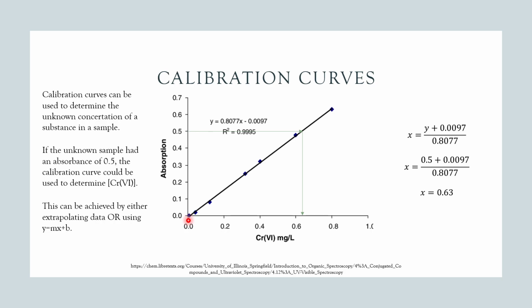So again, you would make up your chromium standards of set concentrations, put them into the spectrometer, figure out what all their absorbances are, and make a calibration curve. And then you would put in your unknown substance. Let's say that the substance got an absorbance of 0.5. What we could then do is plot 0.5 onto the calibration curve and figure out roughly what the concentration would be. Here we can see that it is just over 0.6 milligrams per litre. And that would be a rough estimate for the concentration of chromium that's contaminating our sample.